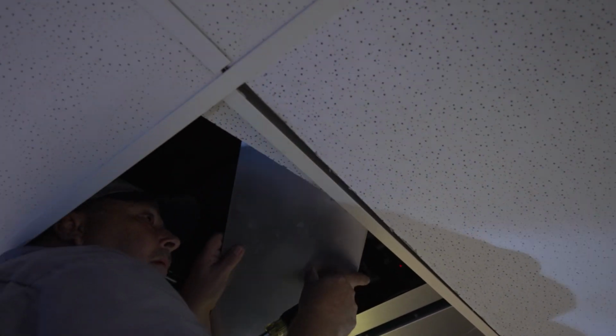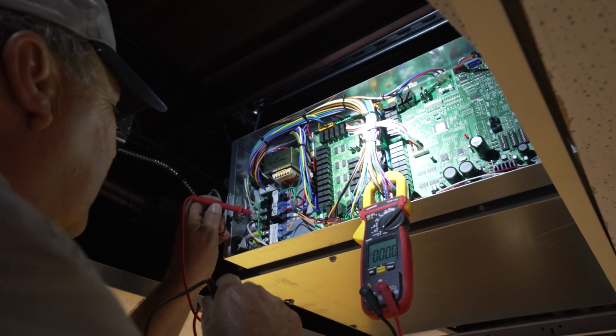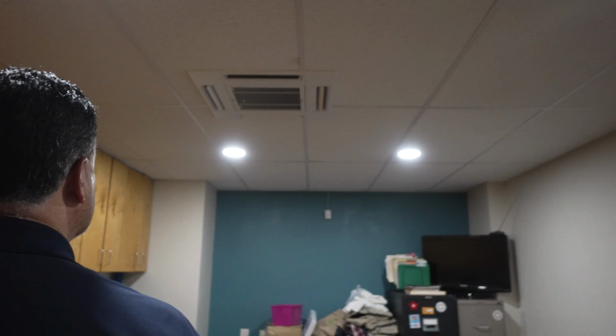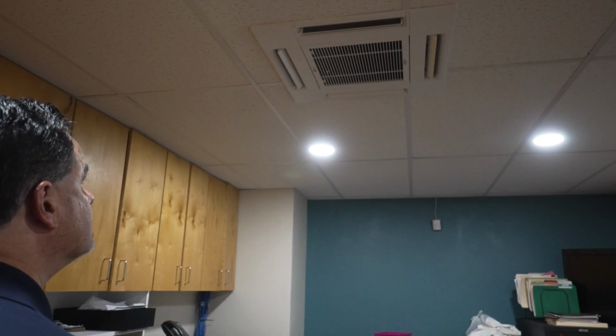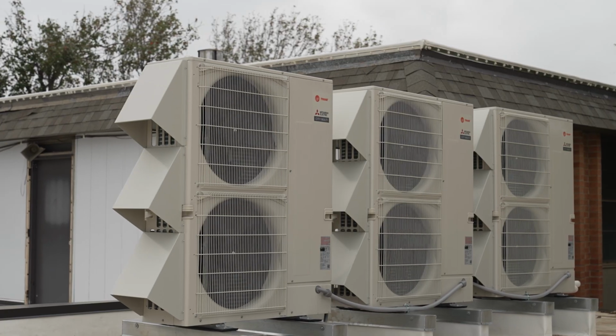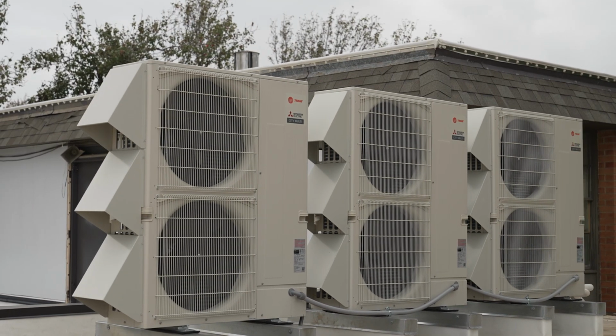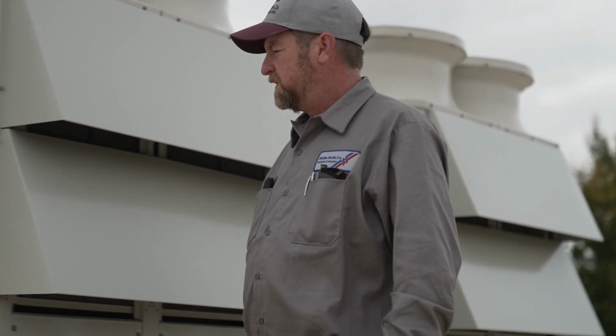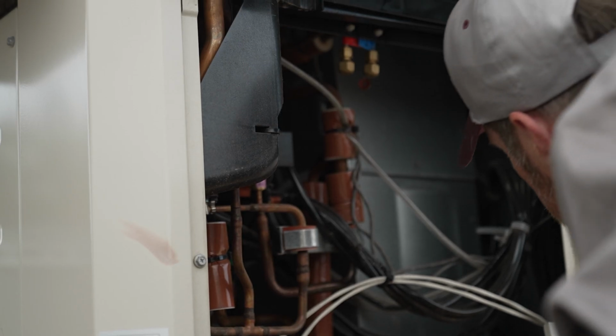So whenever I think about installation with a traditional system, you have a lot of ductwork traditionally involved, a lot of power wiring, a lot of piping. Whereas now with the VRF system, you're just setting cassettes down in the field, setting branch boxes and your outdoor unit. The interconnection is done with just simple copper piping, and the wiring is highly simplified.